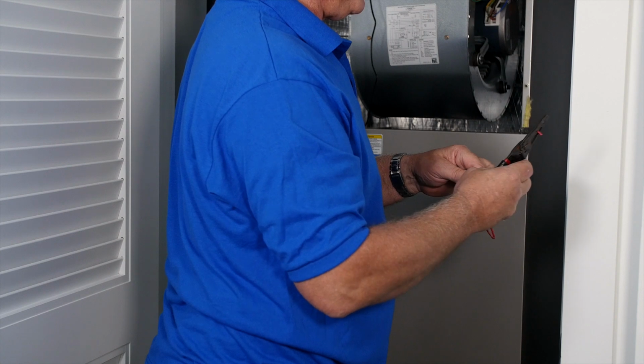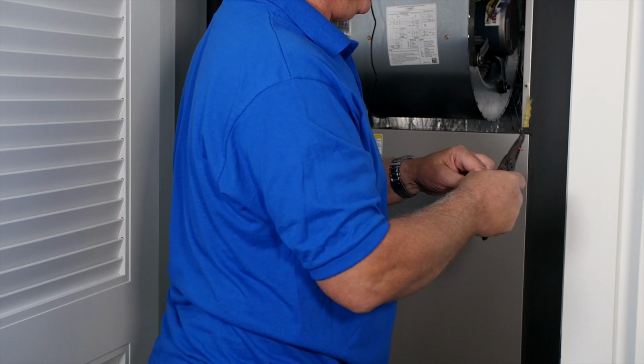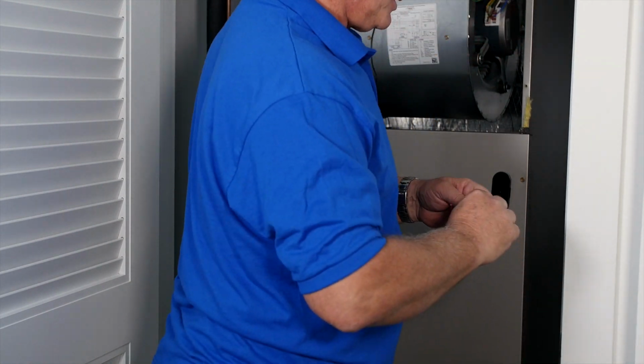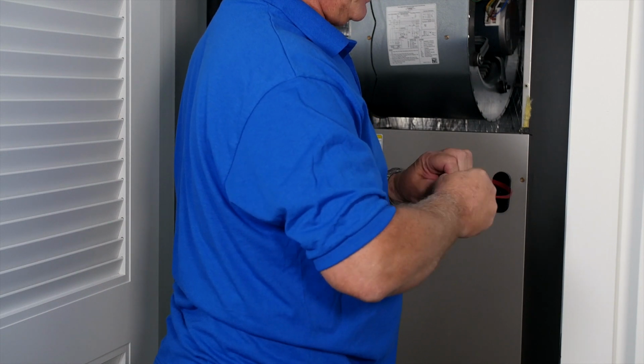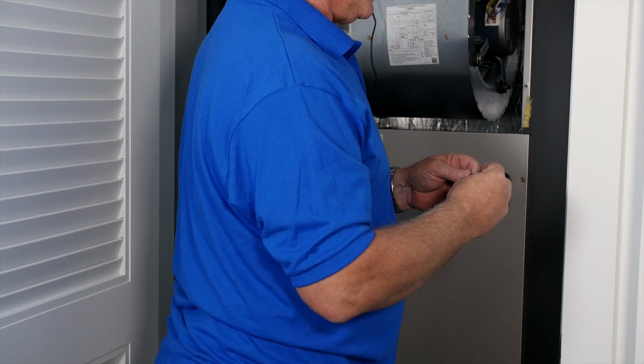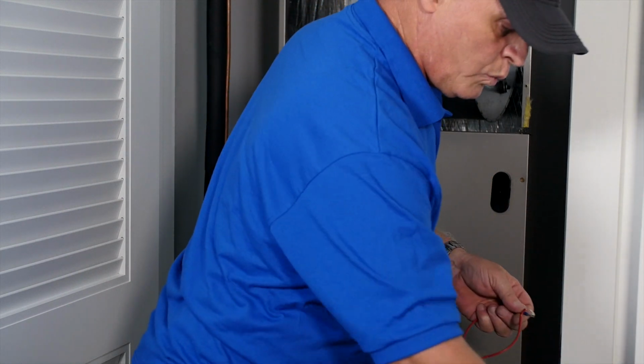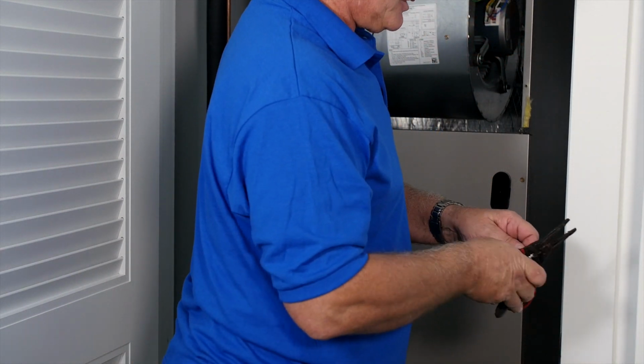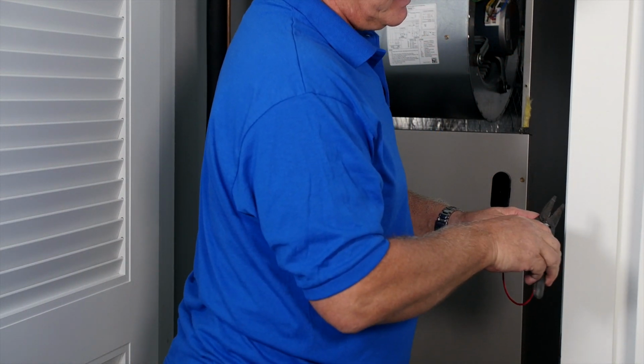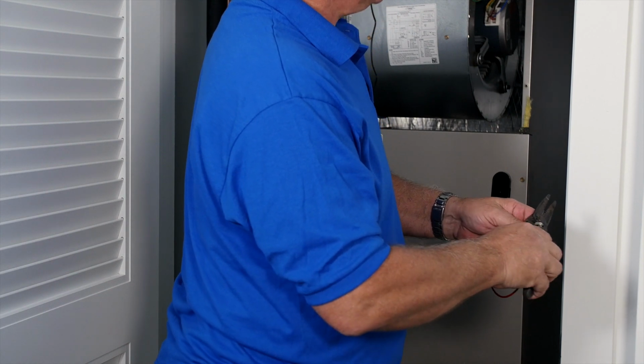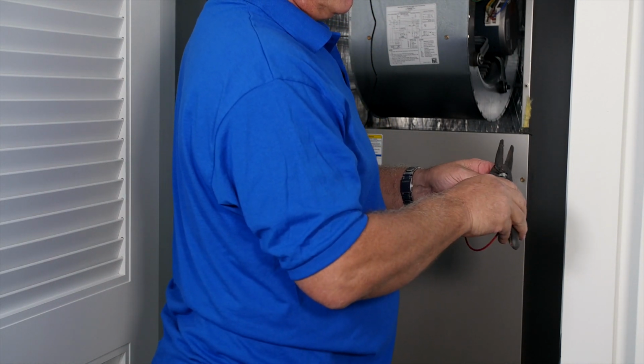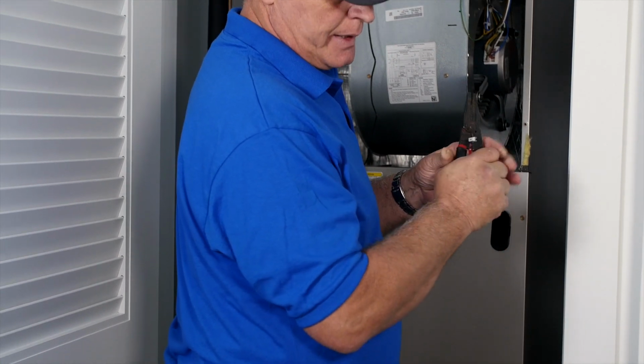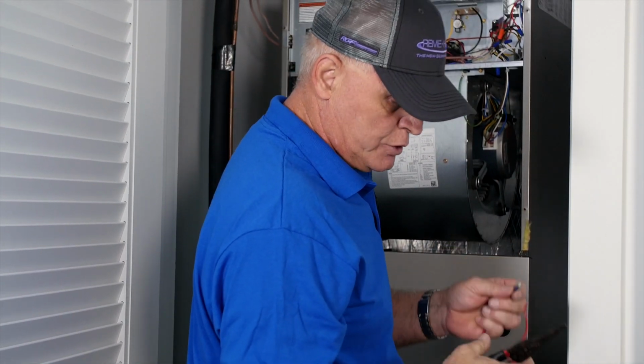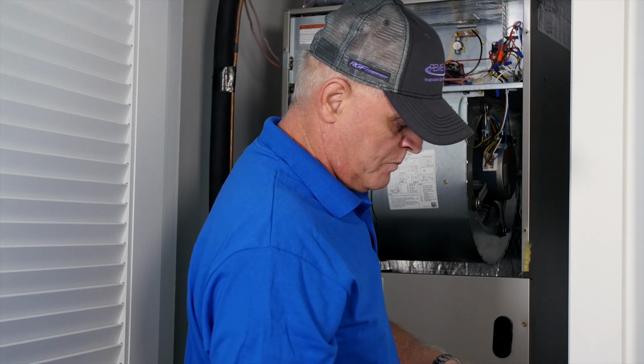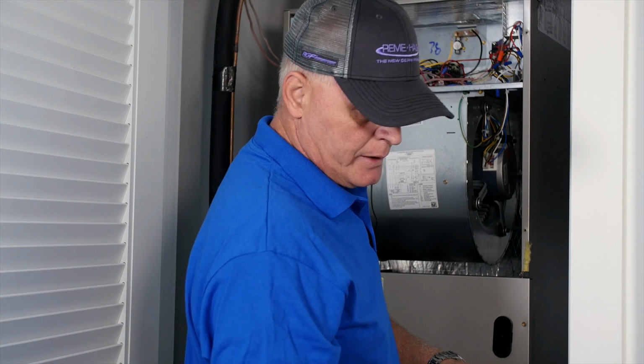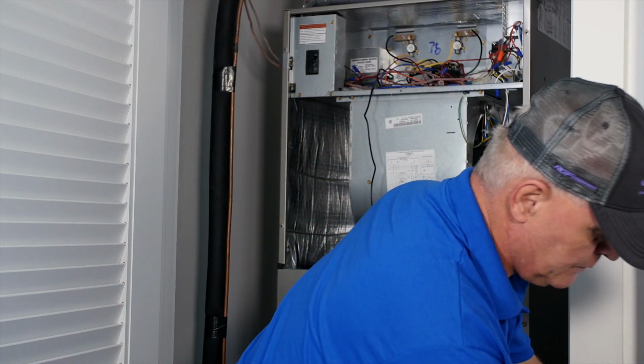There are several different types of these jumpers that you can use. There are some that are just a standalone unit, or you can use the common 1/4-inch plug like this with the extra leg to connect the extra space. Some of the heat sequencer units already have a second leg on them, so you do not need to do this step. It will vary by your air handler that you happen to be doing.